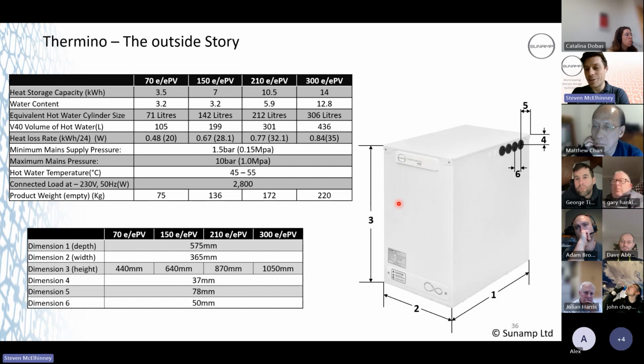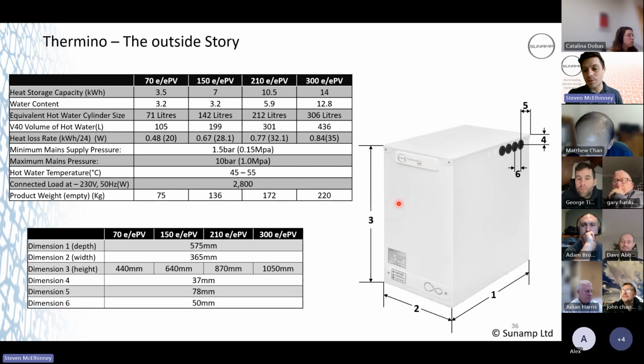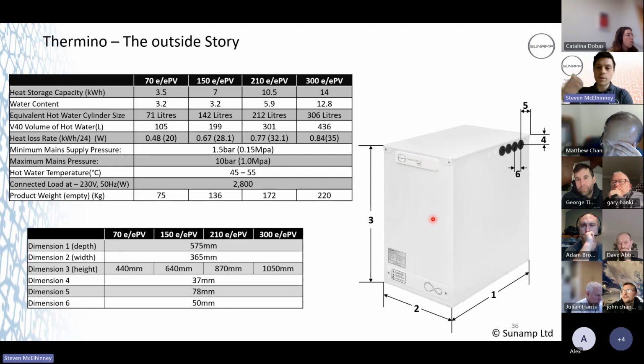I mean, if you've got a secondary return, then you can obviously afford the energy usage, can't you? It depends on the size of the house, but you can do it as long as the customer understands it's going to cost them a bit more, basically, because you've got to get that up to temperature. So your secondary return is going to have to be above 55 on the return. What you could do is have your main unit here, and at the furthest point from the house maybe have a 70, for example, which could boost it at the far end of the house and then circulate back. So it's like you're splitting the difference between the two sides of the house instead of relying on that one unit. So that's another way around.